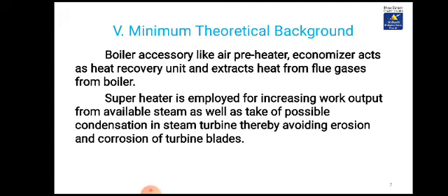Minimum theoretical background: boiler accessories, like air preheater and economizer, act as heat recovery units and extract heat from flue gases from the boiler. Superheater is employed for increasing work output from available steam as well as taking off possible condensation in the steam turbine, thereby avoiding erosion and corrosion of turbine blades.